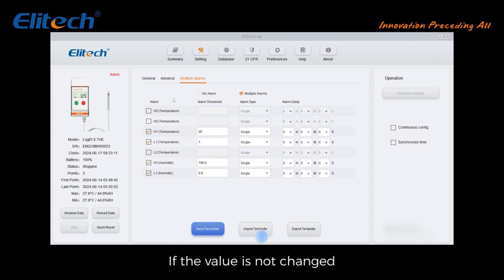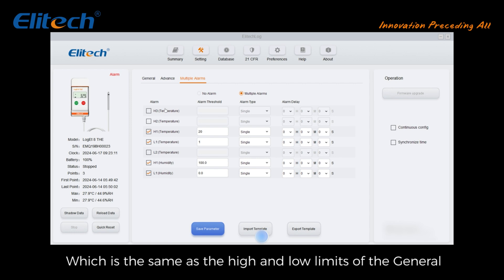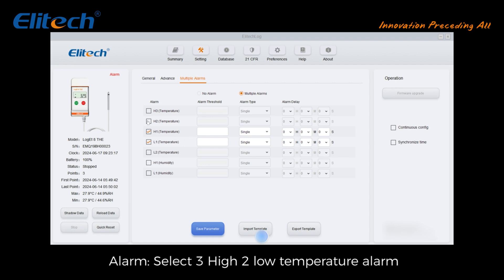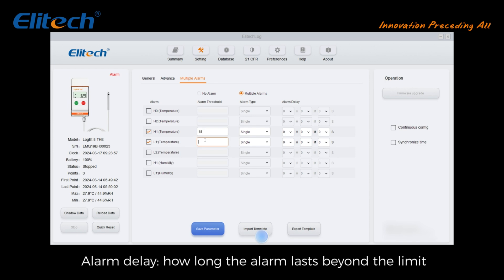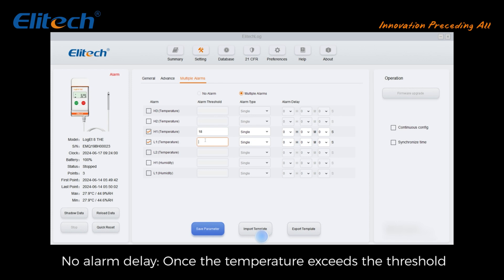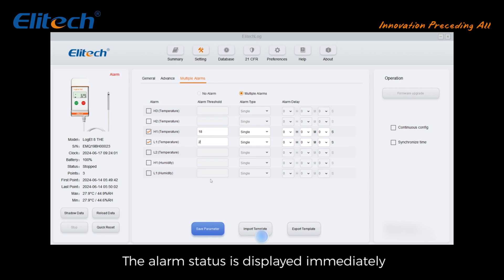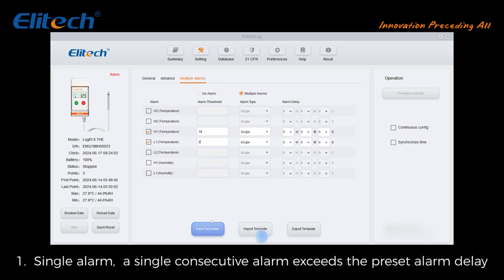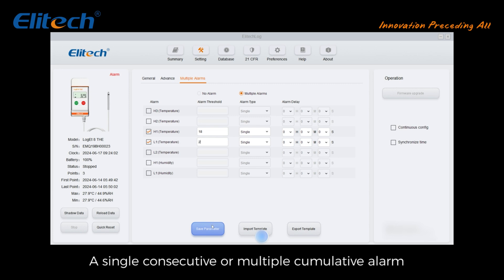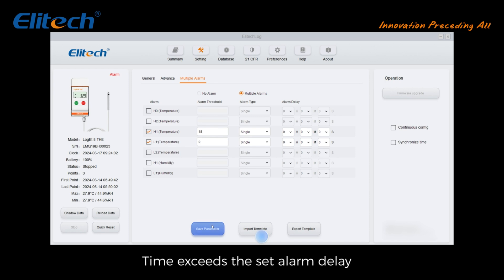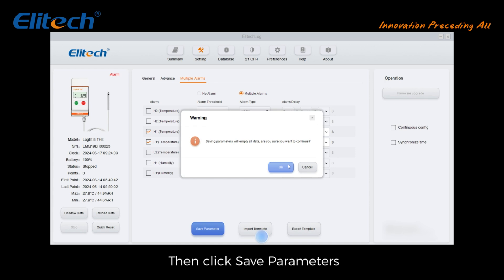Set whether to allow circular logging — when data is full, new data overwrites old data. Click 'Multiple Alarms': if the value is not changed, the default is one high and one low, same as the general alarm limits. Select 3 high, 2 low temperature alarm thresholds with upper and lower limits. Set alarm type: single or cumulative. Set alarm delay — how long the alarm lasts beyond the limit. No alarm delay means once the temperature exceeds the threshold the alarm status displays immediately. Single alarm: a single consecutive alarm exceeding the preset delay displays the alarm status. Cumulative alarm: single consecutive or multiple cumulative alarm time exceeding the set delay displays the alarm status.